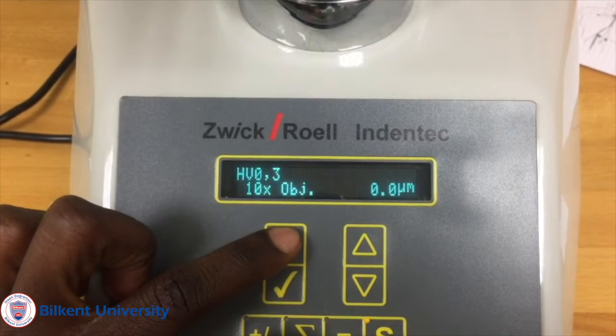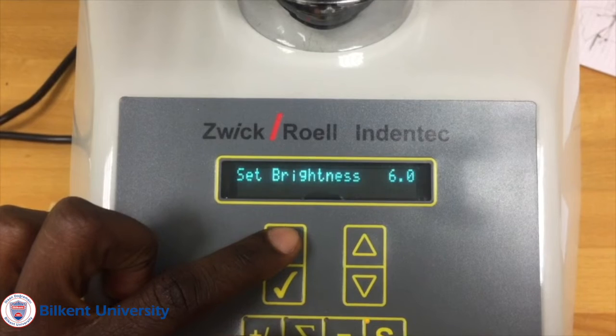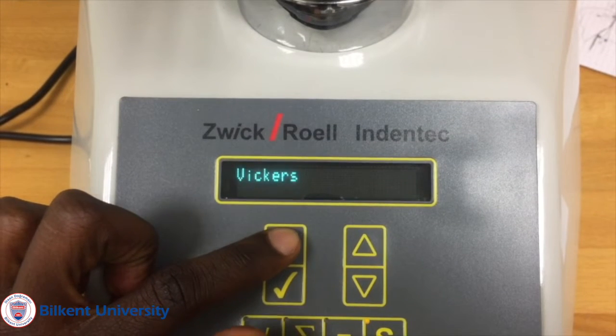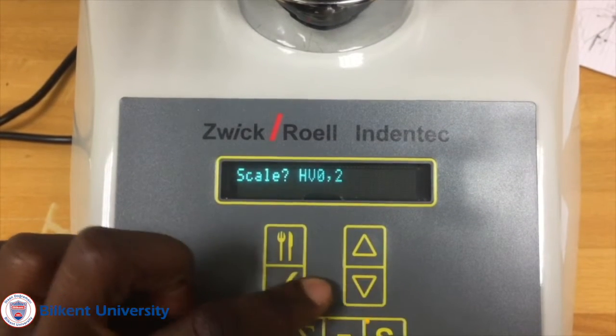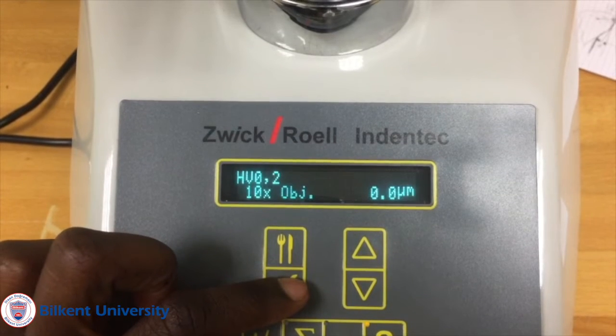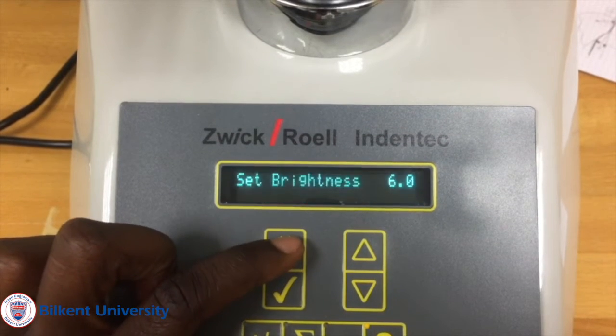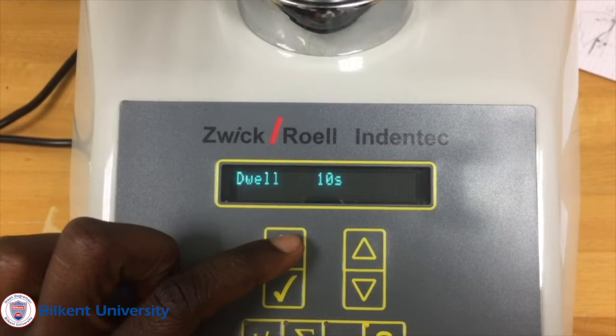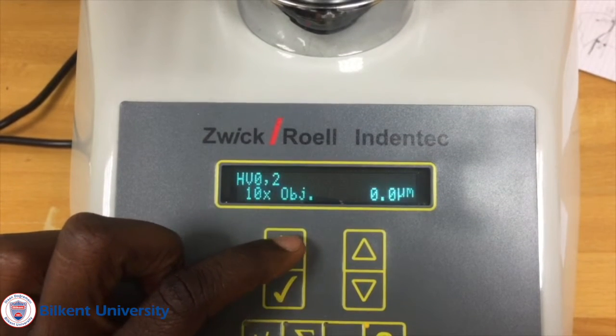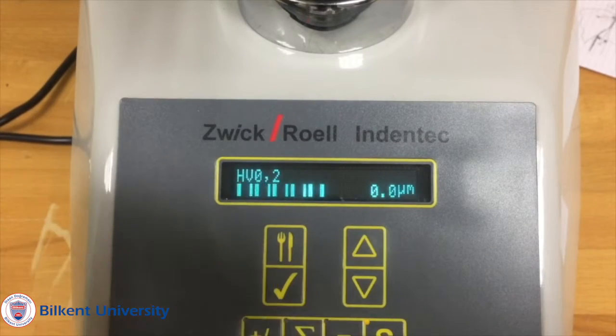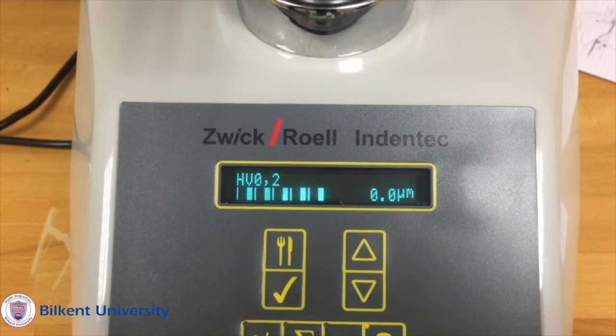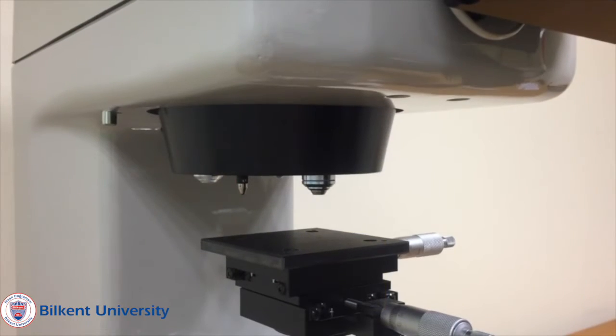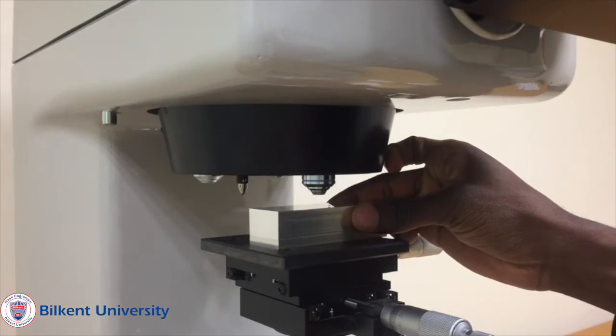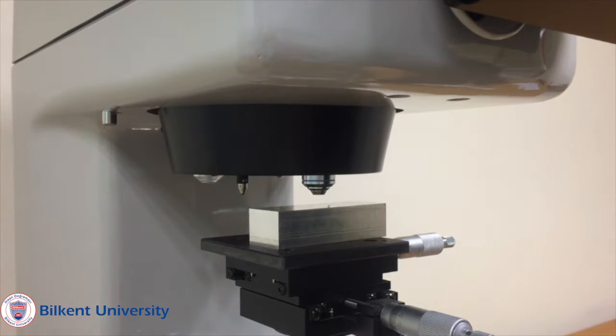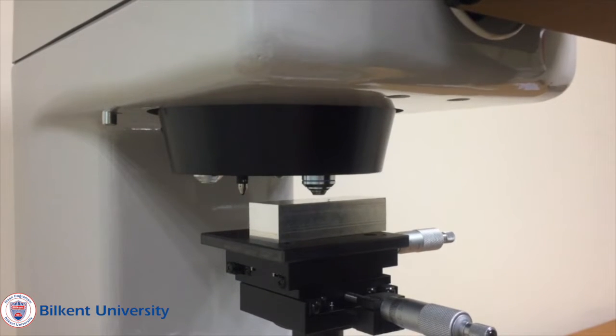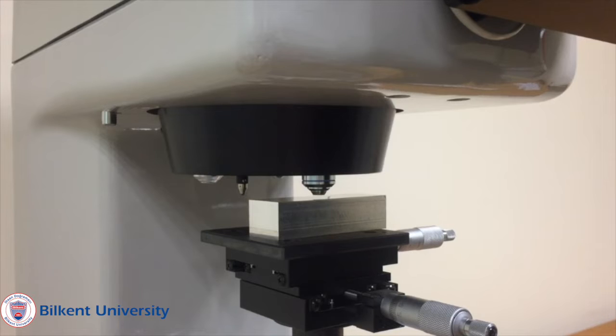Next, we will need to set up the test conditions. To do this, we would move over to the force settings and select a force of 0.2 kilogram force. Now the system indicates that we're working with a 10 times objective lens. We would need to change that to the 40 times objective lens. Once we have set the testing conditions, we can now place the sample underneath the lens and adjust the stage. We should adjust the stage until the surface of the specimen comes into focus.